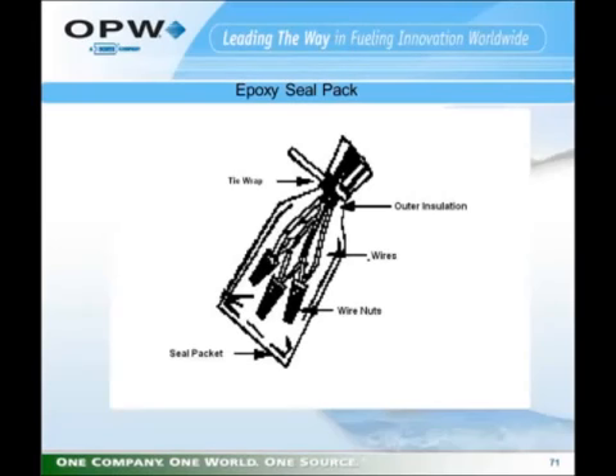Epoxy seal pack that should be used is supplied with the probe. After the wires are stripped, twisted, and wire nutted, they should be inserted in the envelope with the epoxy mixture all the way up to the outer jacket of the cable so that the outer insulation is in the epoxy mixture. This prevents any vapors from traveling below the jacket of the cable into the building, because that would not be stopped by any seal-off that may be installed in the electrical conduit. It also prevents water from corroding the connections and causing stray currents in the junction box.